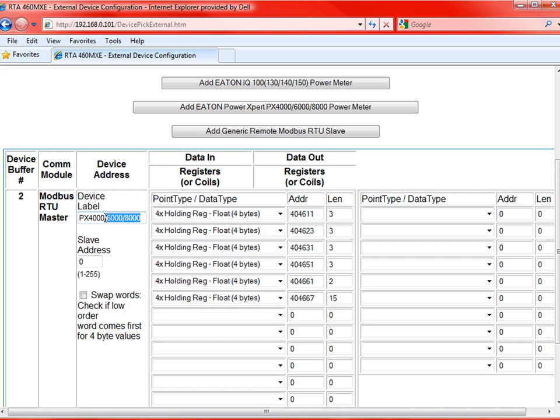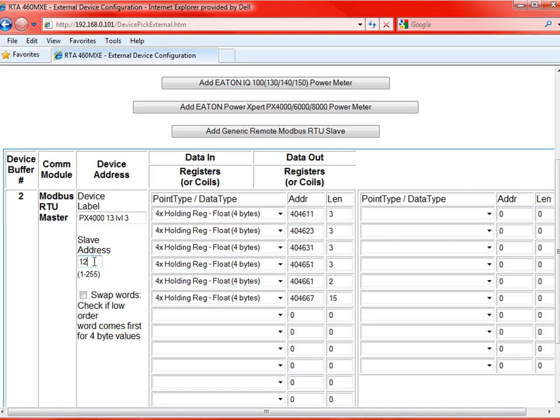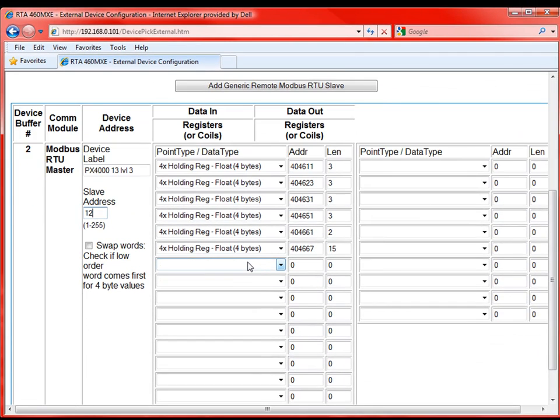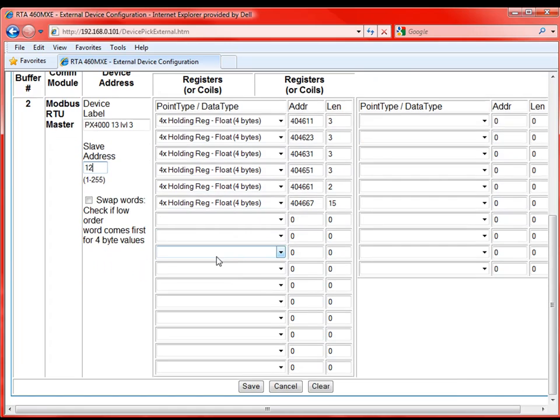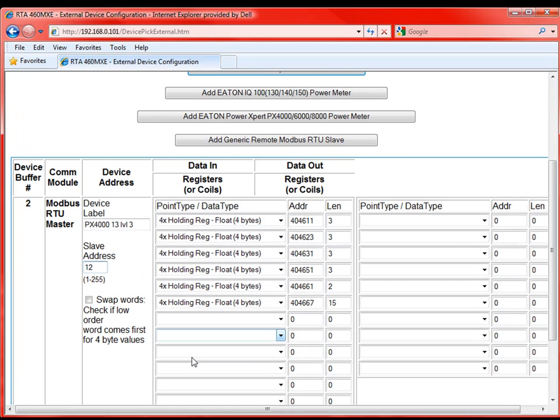If we go into edit within that device, we'll first be able to create a device label. So for this one we said it was a PX4000, let's call this the 4000 meter. We'll just say this is the 13th meter on level 3. The next thing we need to do is give it a slave address. So this is the slave address on the Modbus RTU network. And we'll make this one 12. And this does need to correspond with the device that we're connecting to, so it needs to correspond with the meter.